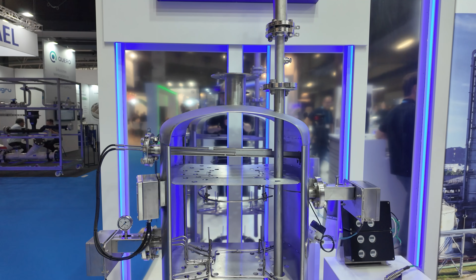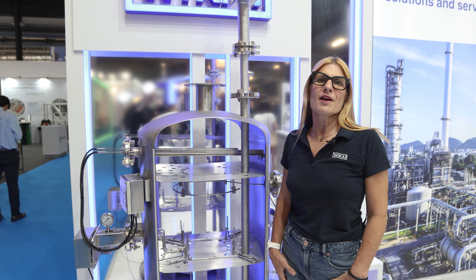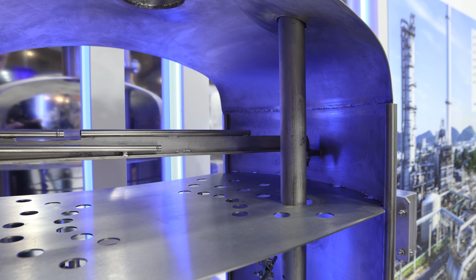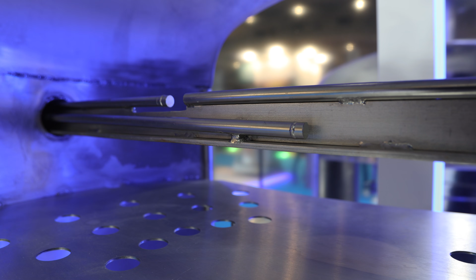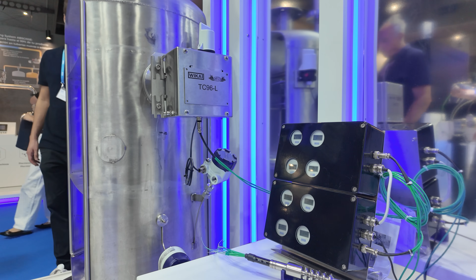We have here our live demo reactor showing the different kinds of multi-points that we offer. We have 3 main types: an individual sheet type, a single-sheet multi-point, and a multi-point type with a thermowell. That last one is for reading the temperature of the beds, where we need to check and ensure homogeneous temperature inside the reactor.